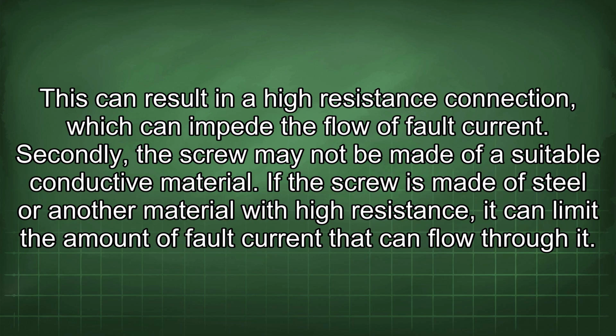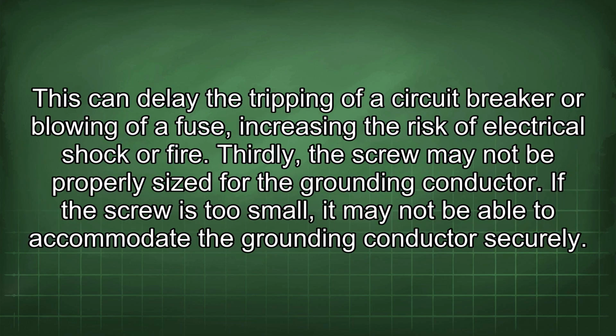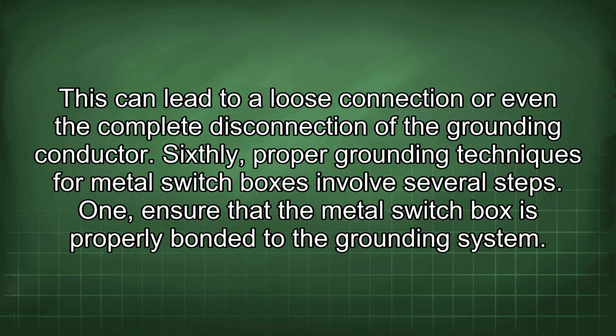Secondly, the screw may not be made of a suitable conductive material. If the screw is made of steel or another material with high resistance, it can limit the amount of fault current that can flow through it. This can delay the tripping of a circuit breaker or blowing of a fuse, increasing the risk of electrical shock or fire. Thirdly, the screw may not be properly sized for the grounding conductor. If the screw is too small, it may not be able to accommodate the grounding conductor securely. This can lead to a loose connection or even the complete disconnection of the grounding conductor.